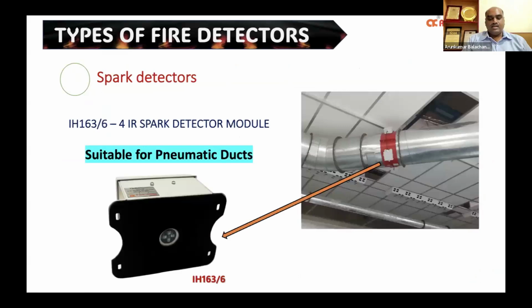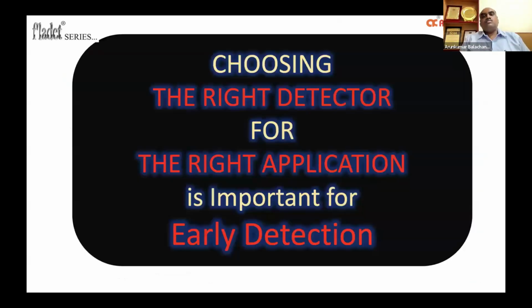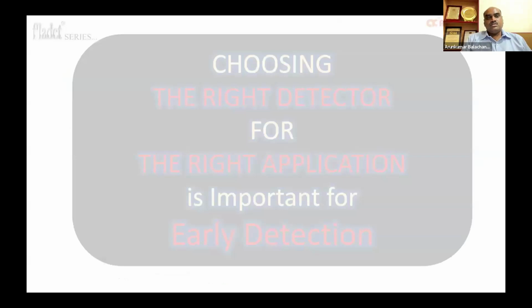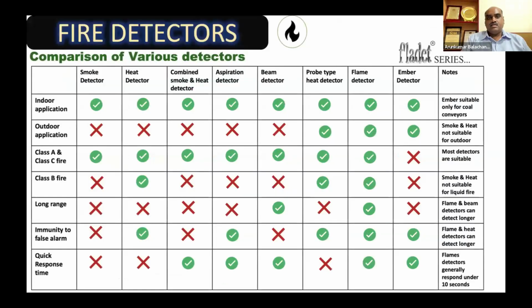The infrared spark detector is mainly used in pneumatic ducts. Again, I will move across this detector. So we come to the major point, that is choosing the right detector for the right application, because that is very much important for our concept of early fire detection. This slide shows the comparison of various detectors, that is smoke, heat, combined or multi-criteria detector, aspiration detection, beam detector, probe type heat detector, flame detector, and ember detector.